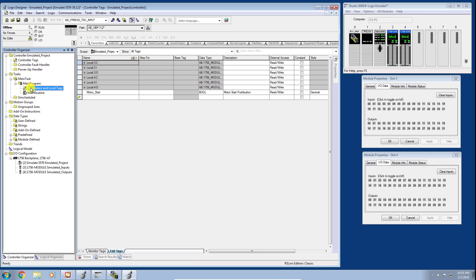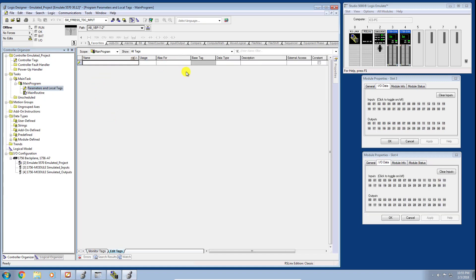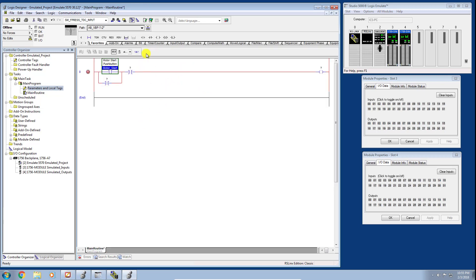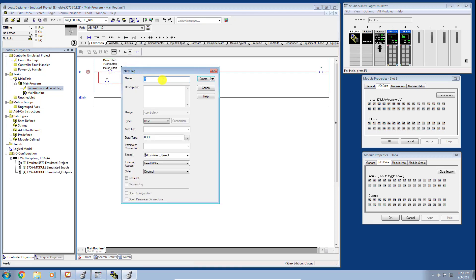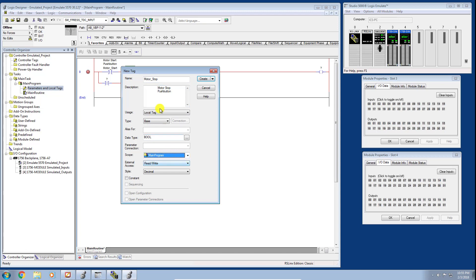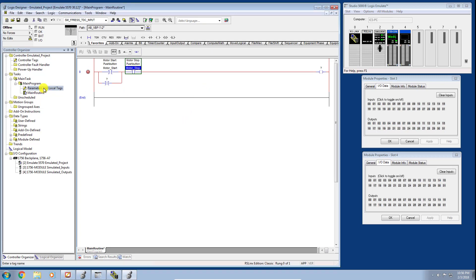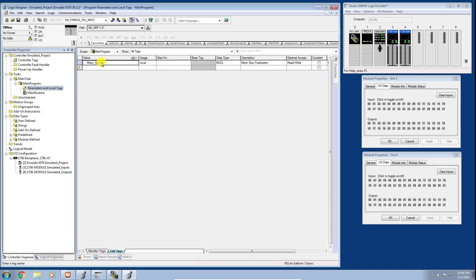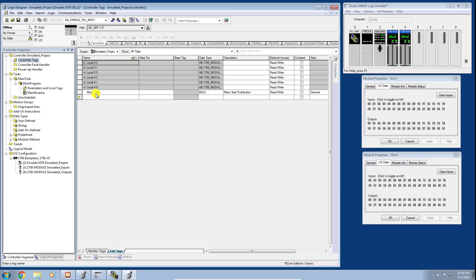For completeness, let's look at the local tag database defined under the Main Program. Every program has its own local tag database, and if I click on that there's nothing in there because we haven't defined a program-scope tag yet. Let's do that now to show the difference — I'll create a new tag called motor_stop with a description of motor stop push button, this time defined as a program-scope tag. You can see it appears in the program's tag database but not in the controller-scope tags.